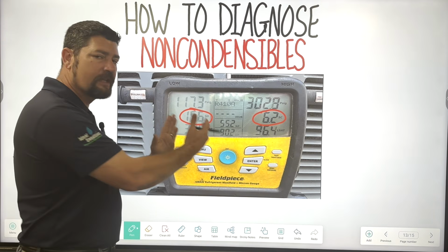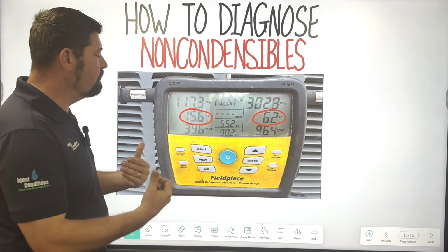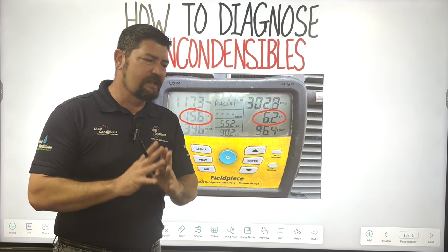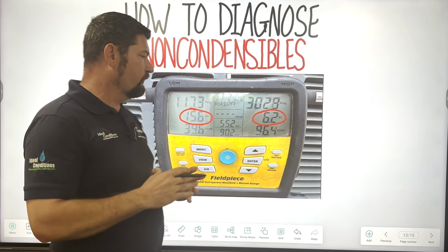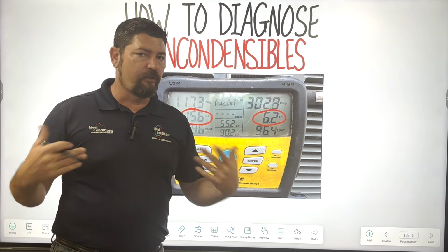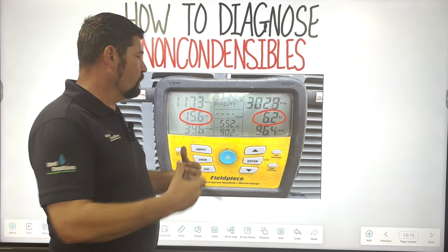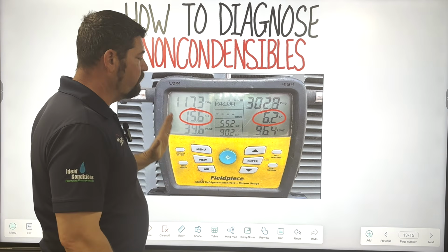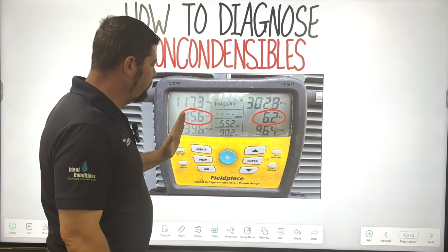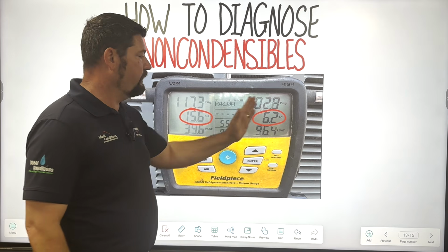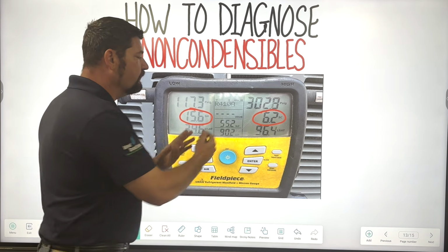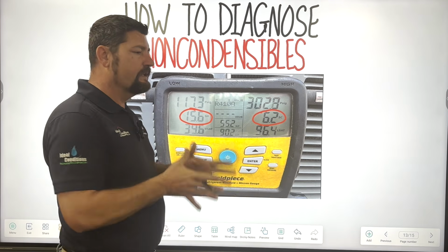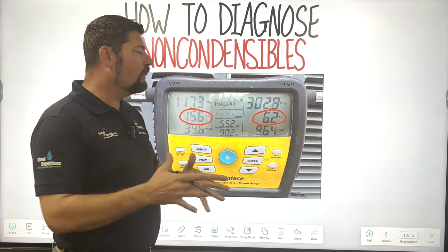And that's the range that I'm looking for. We want to be between that 12 and 18. If we're outside of those ranges, it's not terrible, right? As long as we're not like 28, 30, 25, or if we're maybe 10 or 5 or 0 or a negative number, that would be horrible. So we have vapor returning. We guaranteed that. We have subcool returning. But the problem is these numbers aren't consistent. So if they're not consistent, then there's something else in the system that's causing that.